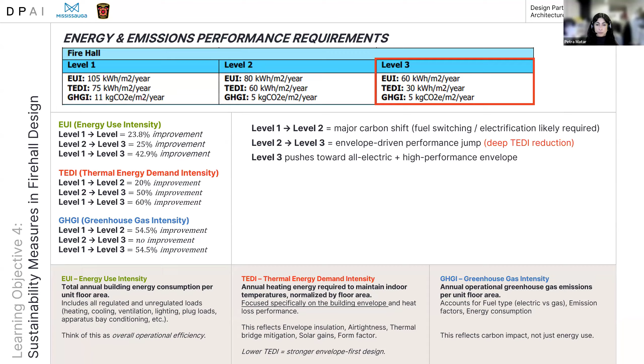For a 24/7 fire station with large apparatus bays, high ventilation rates, and frequent doors opening, a 50 to 60% reduction in TEDI is very significant. That level of reduction requires strong air tightness targets, thermal bridge-free detailing, high-performance glazing, and optimized heat recovery systems. So this is not a single move.